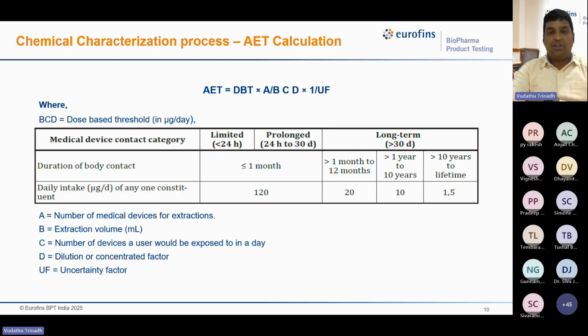And coming to threshold limit setting, which is AET, which is very important for any medical device to determine whether the leachables are below the safety limits or above the safety limits. Basically, AET will be designed based on the formula DBT × A/(B×C×D) × 1/UF, where DBT is the dose-based threshold, which is in terms of μg per day.